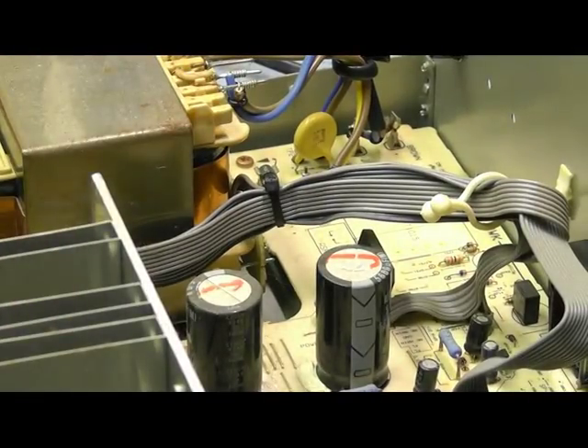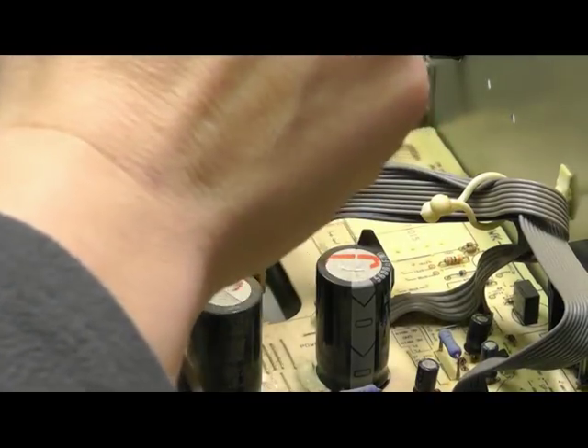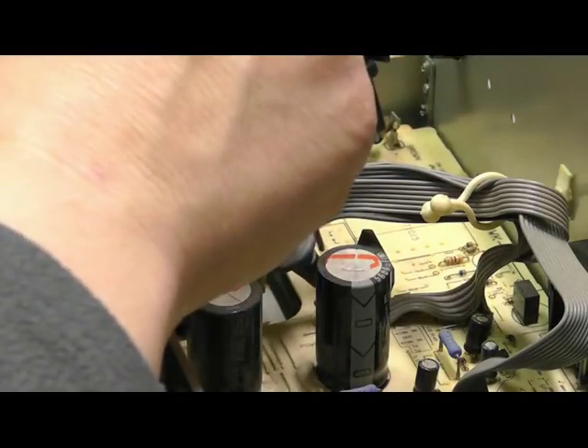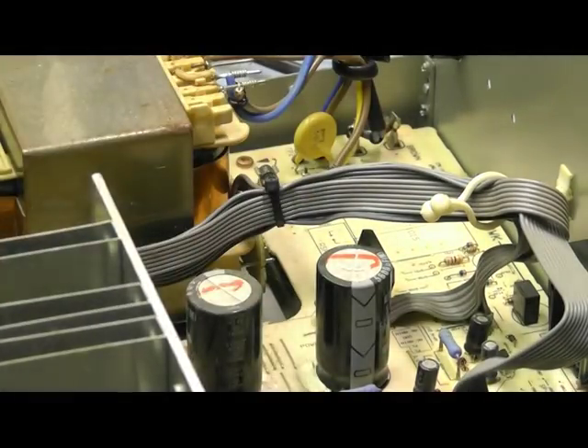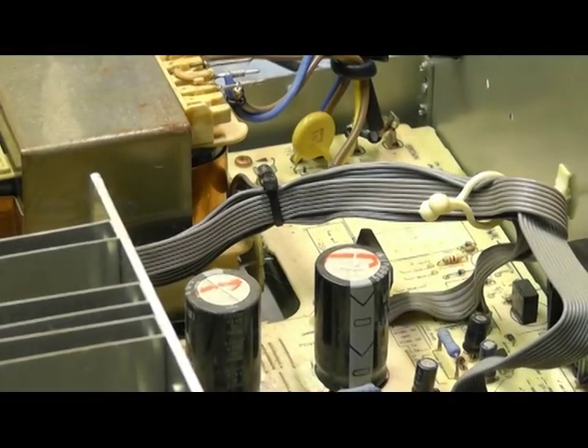Okay, well the transformer's on, I can hear it humming. If I put a screwdriver to it and put it to my ear, I can hear the primary of the transformer's activated, so the primary's not open circuit. Looking on the secondary at the input to the bridge, there's nothing - it's open circuit. So I'll definitely remove the bottom off and check for cracked joints and connections.